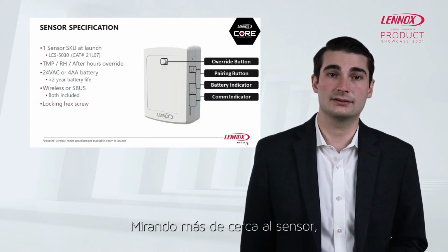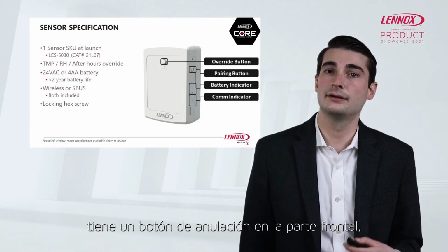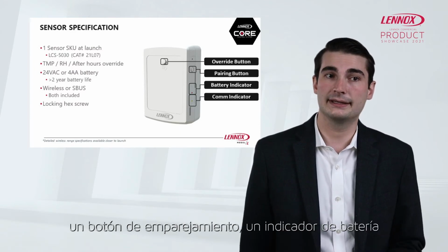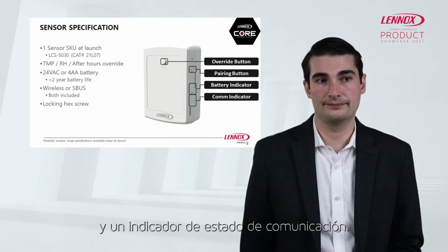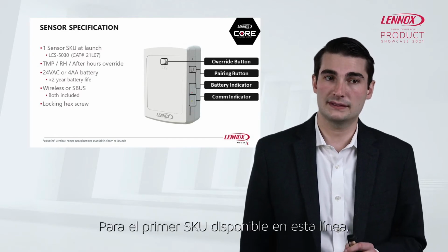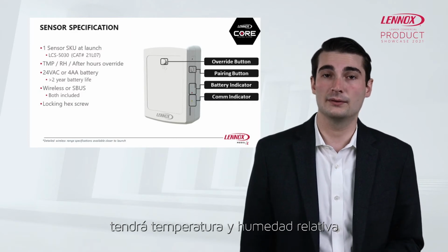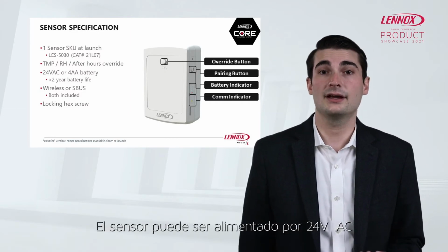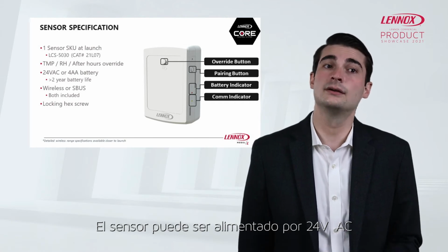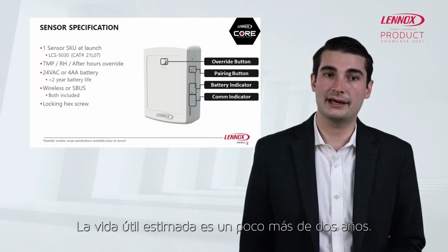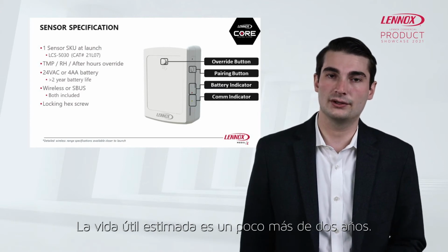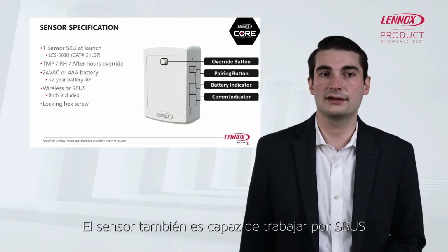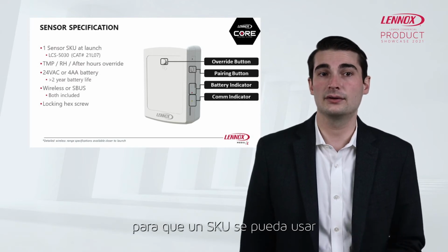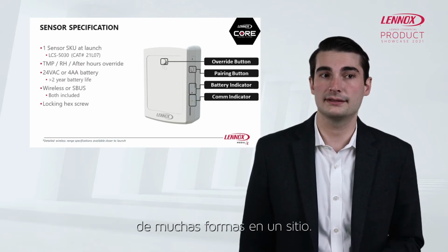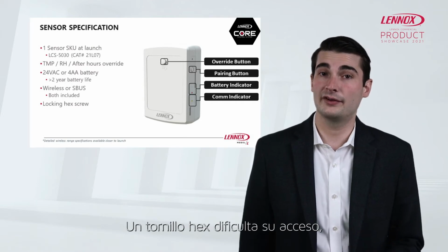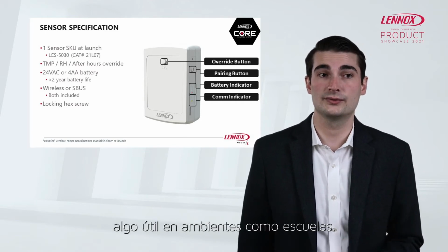Taking a closer look at the sensor, it has a front-mounted override button, a pairing button, a battery indicator, and a communication status indicator. For the first SKU available in this line, it will have temperature and relative humidity built directly into the sensor. This sensor can be powered by either 24 volts AC or 4 AA batteries. On battery, the typical estimated life is just over 2 years. The sensor is capable of also working via S-Bus, so that one SKU can be used in a multitude of ways on one site. An end-set locking hex screw prevents access in environments such as schools.